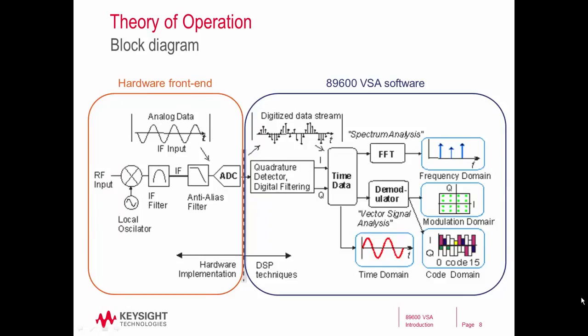Here in this diagram, we can see how the hardware front end and the 89600 VSA software are working together. In the orange rectangle on the left, we have our representation of the acquisition being made by the hardware, which is then passed to the 89600 VSA software. All of the operations being done in the software are contained within the blue rectangle on the right. The VSA software gets the time domain data from the hardware front end, then performs the FFT, demodulation, and various transforms to provide different data formats, displaying results in the frequency domain, modulation domain, code domain, and time domain.